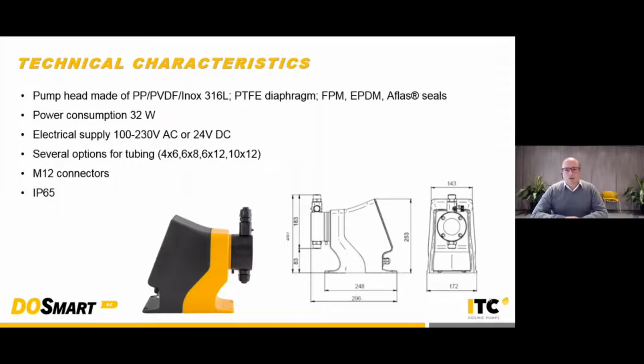The electrical supply can be single phase, 110 or 230 volts AC at 50 or 60 hertz, or can be 24 volts continuous. As I said before, we have also adapted and modified our fittings and valves. So we have several options for tubing, 4x6, 6x8, 6x12, 10x12, all of them available. However, there is a recommended size for each flow of the pump. In order to get the best connectivity, the connectors we are using are standard M12 connectors. And all of this is IP65.